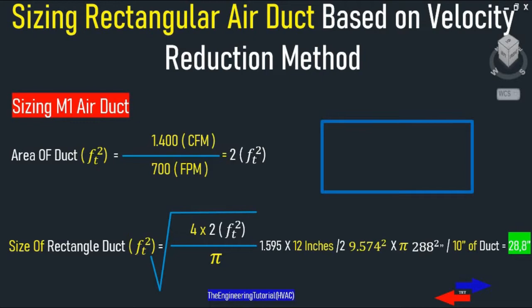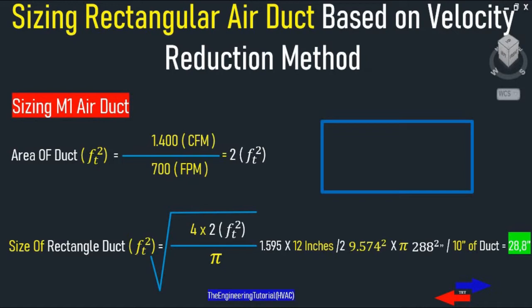So 288 square inches can be divided by the height or width of the main supply duct. Based on your own needs, you can determine how many inches the height of your duct needs to be. For example, let's say we want the height of our main supply duct to be 10 inches, so its width would be 28.8 inches. We simply divide 288 square inches by the height of 10 inches.